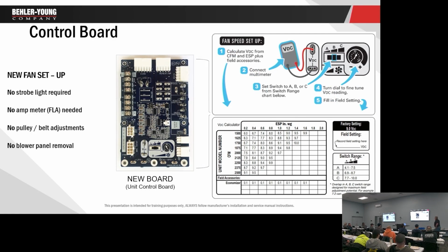Now we're going to talk about setting this blower up. It is not factory set. If you don't set the blower up on this thing, remember that safety circuit that I said was inside this motor? If it decides that it's drawing too much amperage or too little, whatever, it will shut itself down. It will open the safety circuit and shut itself off. It doesn't mean the motor's failed.